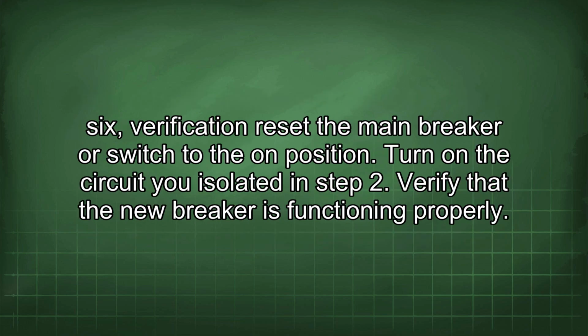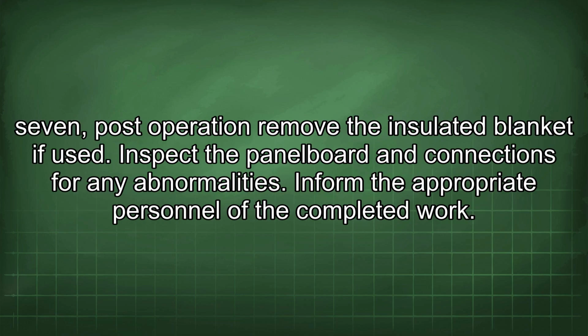6. Verification: reset the main breaker or switch to the on position. Turn on the circuit you isolated in step 2. Verify that the new breaker is functioning properly. 7. Post-operation: remove the insulated blanket if used. Inspect the panel board and connections for any abnormalities. Inform the appropriate personnel of the completed work.